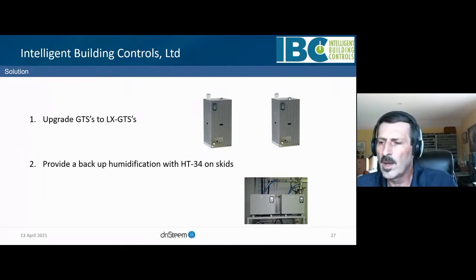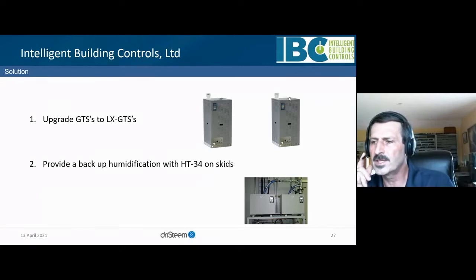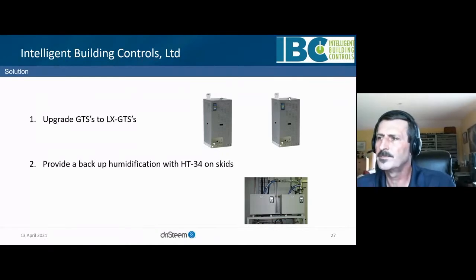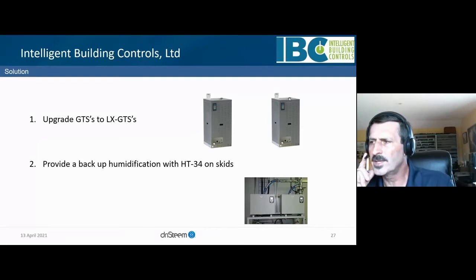The decision with the client was to upgrade to the new GTS LX humidifiers, which are fully condensing and low NOx, providing a more energy efficient and environmentally friendly solution, and to pair these with our HT series resistive humidifiers for high accuracy and redundancy. In addition to upgrading to high-efficiency gas generators, the existing dispersion tubes were already high-efficiency insulated units that reduced condensate to drain with resulting energy and water savings.